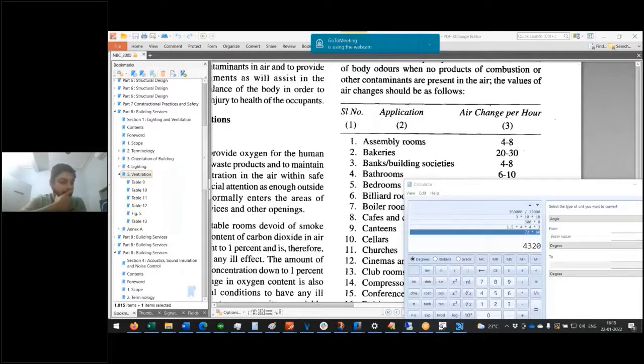If I selected a fan with a particular CMH and divided this value by that, I got 8 numbers. Can I say that's 4 plus 4, 4 exhaust and 4 fresh air, or do I have to put 8 plus 8? No, you have to put 8 plus 8. Fine, 8 plus 8 mechanical fans. If I do ducting, the case will change. Yeah, that's also fine. You can do ducting, you just have to take into account the duct friction losses. Okay, losses also we have to add to this.